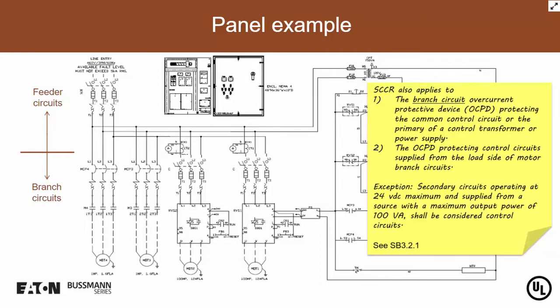Now, there are some exceptions. We are going to be looking at all of the branch circuits and feeder circuits on the power side of things. We don't want to look at the control side of things. And you're asking, well, what is the control side? I'm not going to get into the details of that yet because we don't have that much time in this 1 hour presentation, but we're going to look at all power circuits in general. Now, there is an exception that says no matter what the load is, on the secondary side, circuits operating at 24 volts max and supplied from a source that has an output of 100 VA, so basically a power supply that's 24 volt output and no more than 100 VA, no matter what is feeding it, it's always considered a control circuit and is not considered in the SCCR determination. Right?